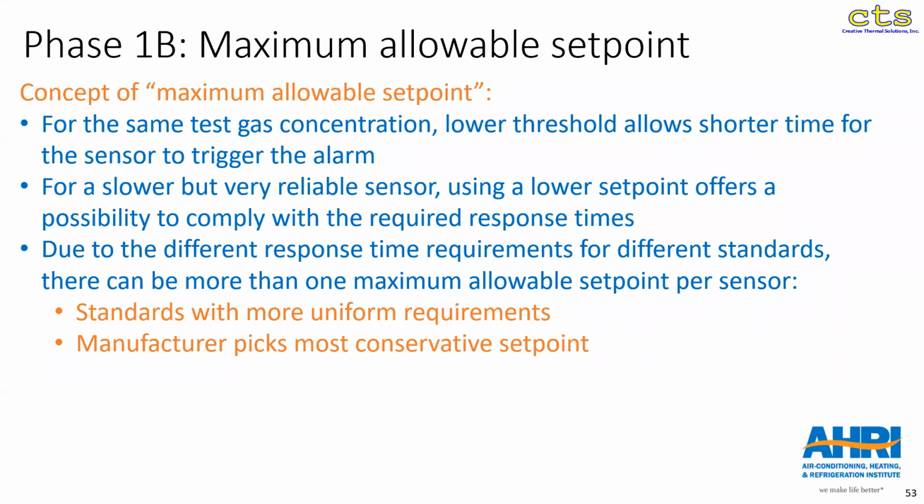The issue we have identified here is that because in the different standards, we see different time requirements that are listed in the individual standards. There will be more than one maximum allowable set point. Sounds a little bit confusing, but maybe in the next slide you will see what I mean. So definitely what would be helpful is if the standards are a little bit more uniform in terms of their requirements, or the manufacturer is able to pick the most conservative set point to address the standards of interest. Next, please.